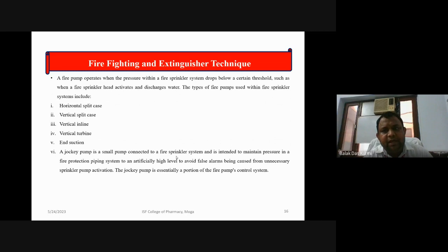The types of fire pumps used within fire sprinkler systems include horizontal split case, vertical split case, vertical inline, vertical turbine, and end suction. A jockey pump is a small pump connected to a fire sprinkler system and is intended to maintain pressure in a fire protection piping system at an artificially high level to avoid false alarms being caused from unnecessary sprinkler pump activation. The jockey pump is essentially a portion of the fire pump control system. Although this topic is related to the HVAC side of the industry, I am giving just the introductory part, as this is related to the engineering part of any organization.